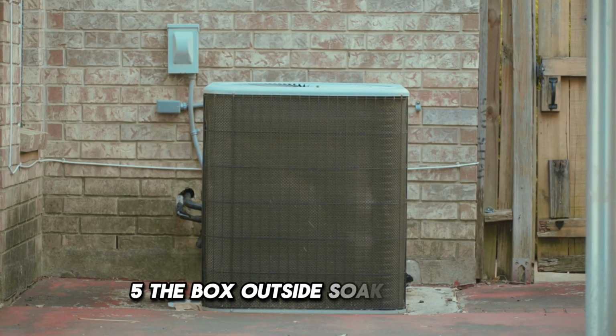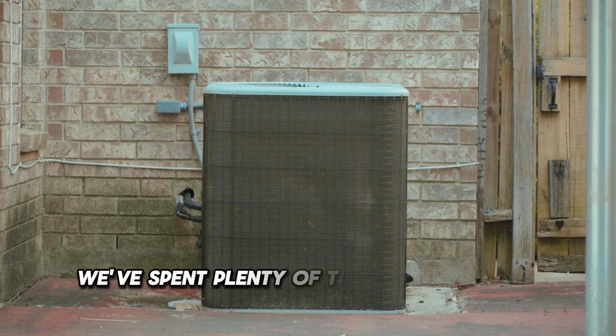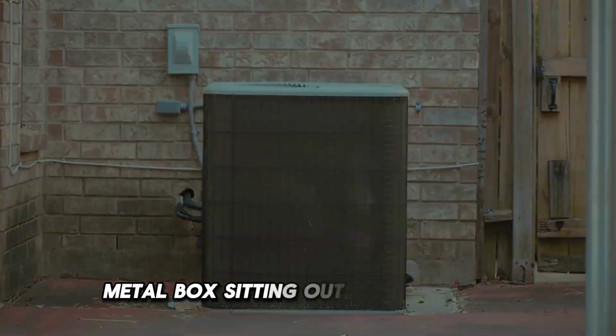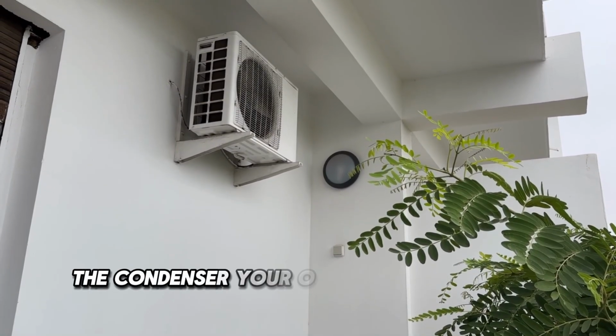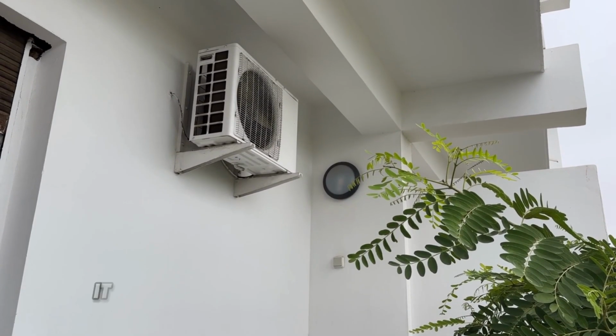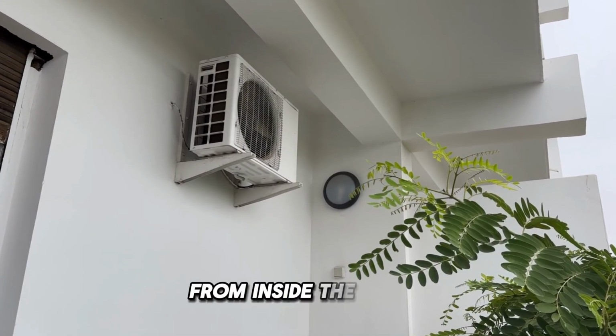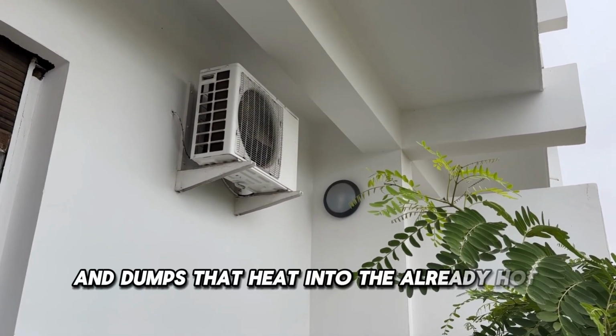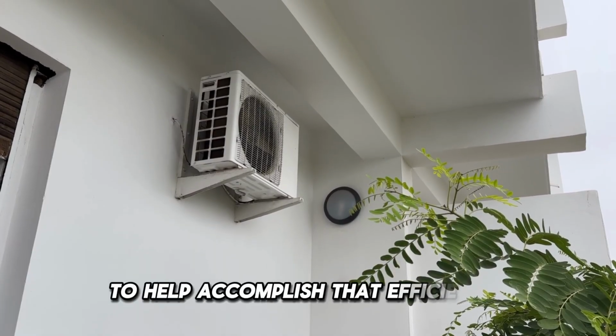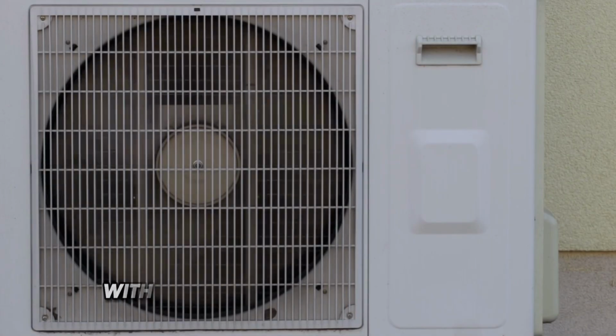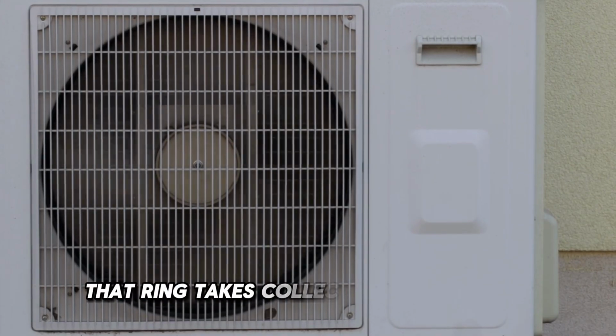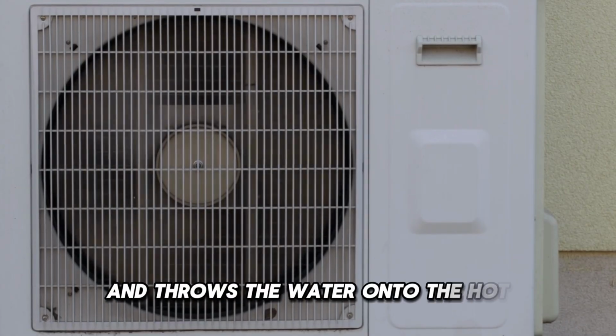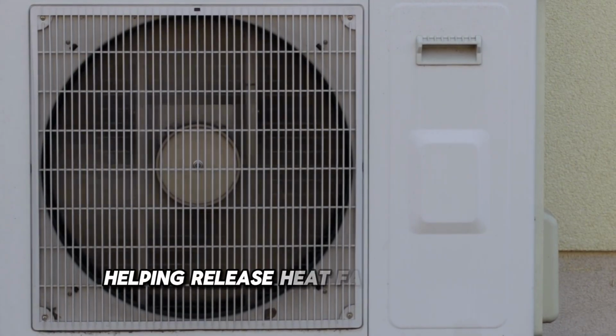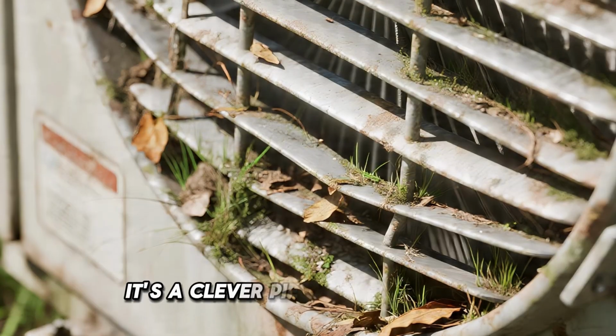5. The box outside soaking itself. We've spent plenty of time talking about the indoor side of your system, but we can't ignore that big metal box sitting outside in the yard. The condenser. Your outdoor unit has one hard job. It takes the heat your system removed from inside the house and dumps that heat into the already hot outdoor air. To help accomplish that efficiently, many modern systems are equipped with something called a slinger ring attached to the fan blade. That ring takes collected condensation and throws the water onto the hot outdoor coil, helping release heat faster through evaporation. It's a clever piece of engineering.